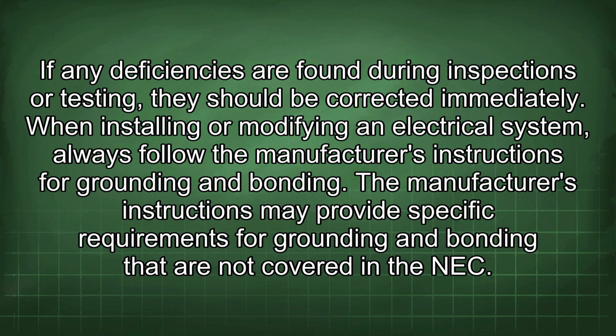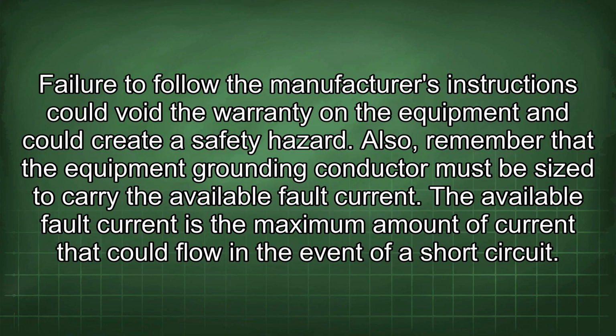When installing or modifying an electrical system, always follow the manufacturer's instructions for grounding and bonding. The manufacturer's instructions may provide specific requirements for grounding and bonding that are not covered in the NEC. Failure to follow the manufacturer's instructions could void the warranty on the equipment and could create a safety hazard.